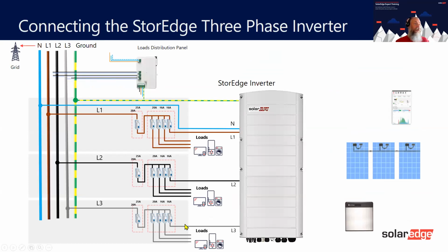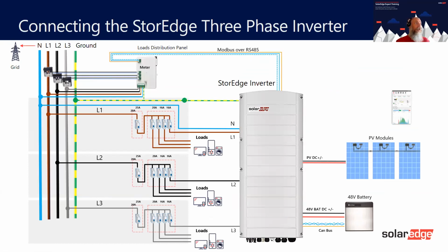It's 3-phase, so you have 3-phase loads, obviously. Your battery here, again, 5 meters is the maximum distance. PV as well. You must make sure, very important, that the L1 CT is in L1, L2 is on L2, and L3 is on L3. And here is your RS485 communication. And the last bit is the communication to the monitoring. This can be Wi-Fi, it can be Ethernet, it can be GSM cellular, and all that will communicate to the monitoring portal. Again, it's all free of charge.